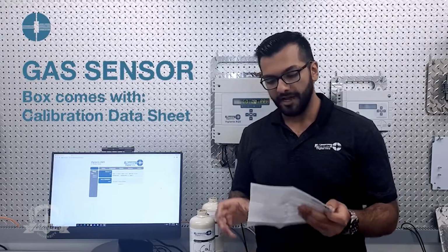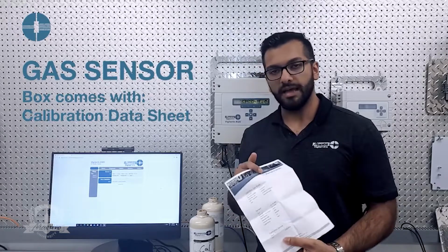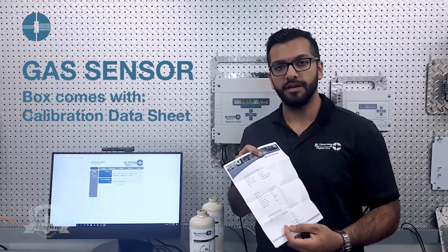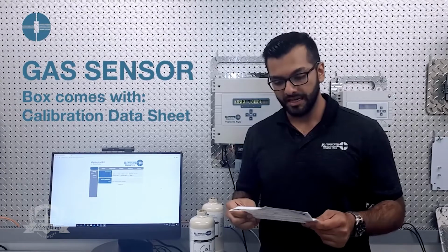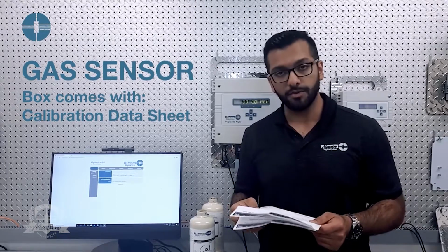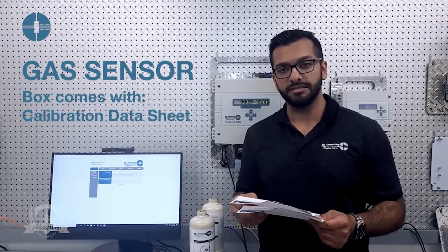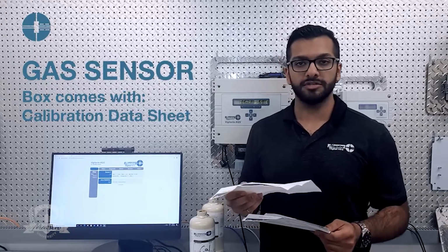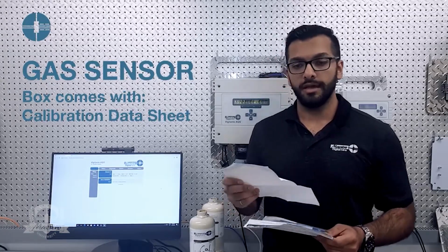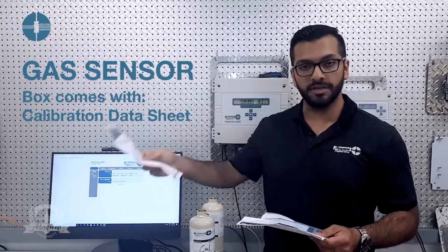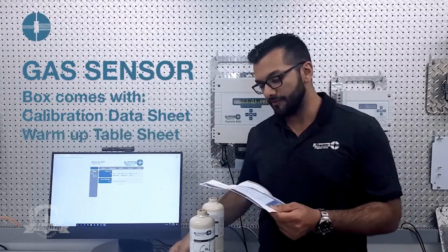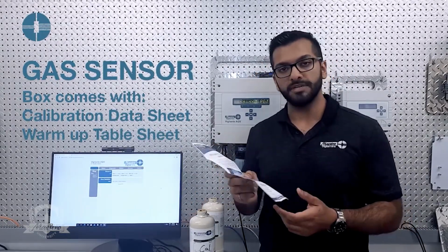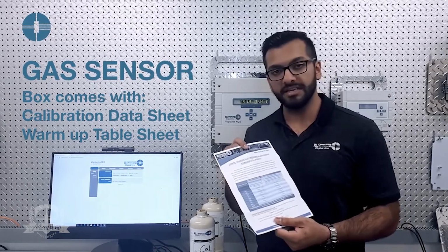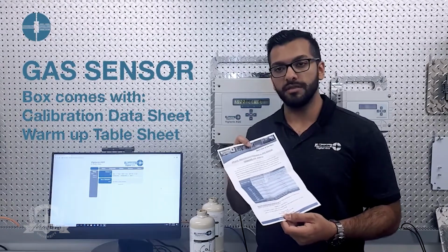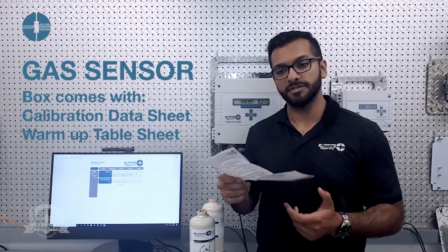So first thing we have here is the gas sensor calibration data sheet. What this gives you is information about the calibration bottle that has been used for the gas sensor, as well as other information such as the factory calibration date used on the gas sensor. And the next piece of information provided is the warm-up table, as well as any updates that you might see with the gas sensor itself in terms of functionality.